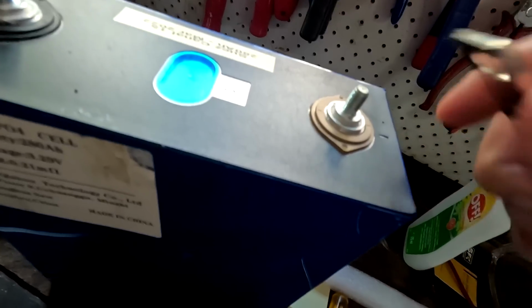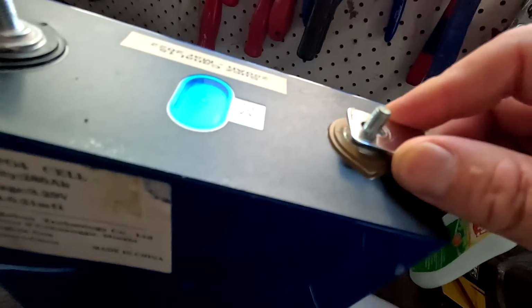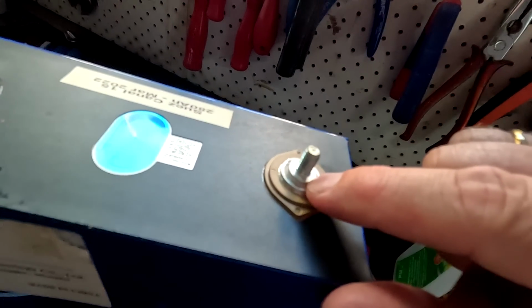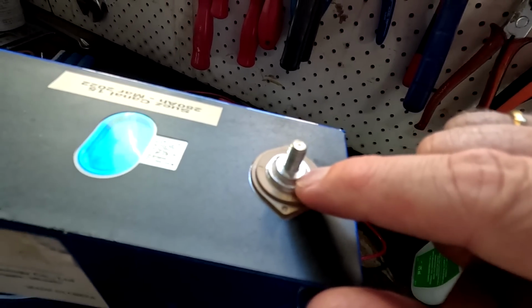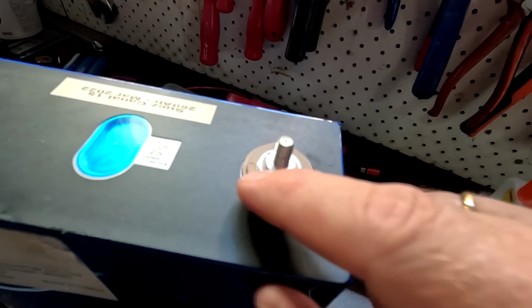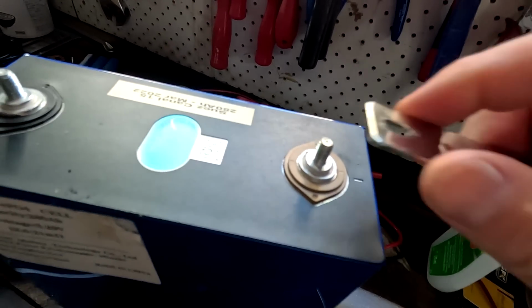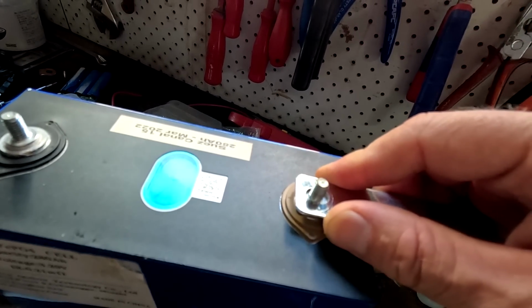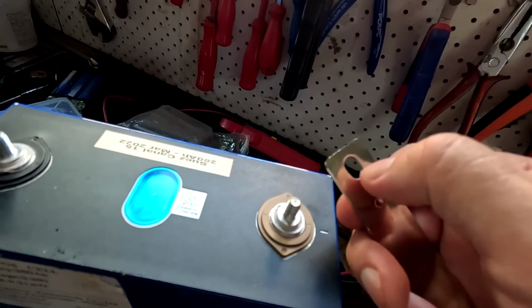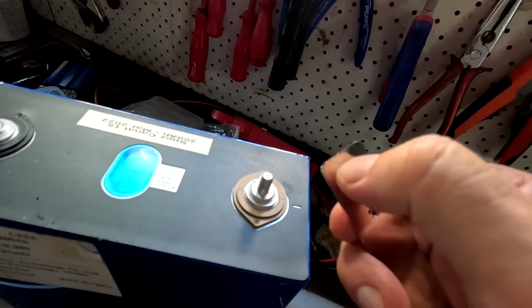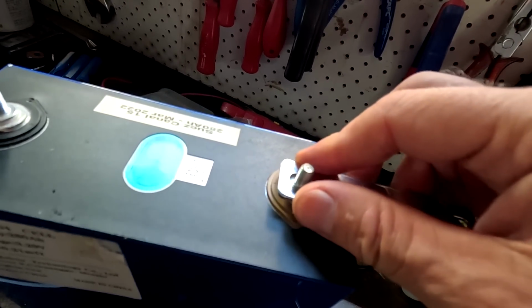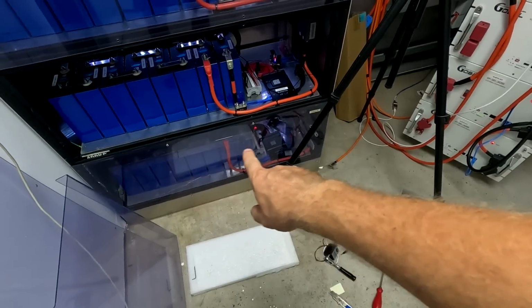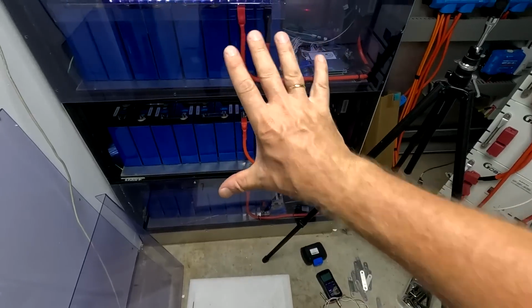But if we put this bus bar on top of this welded terminal, we have only a very small contact area, because this plateau here at the top has a very small area in comparison to the actual full terminal of this cell. But then when you torque it down with 4 Newton meters, you put very high pressure on this smaller area, and the resistance is so low that my battery number 3 here in the bottom shelf is actually the best in the whole battery shelf.